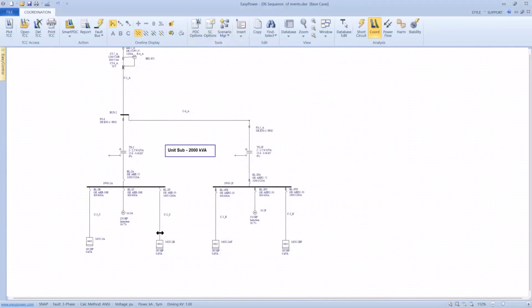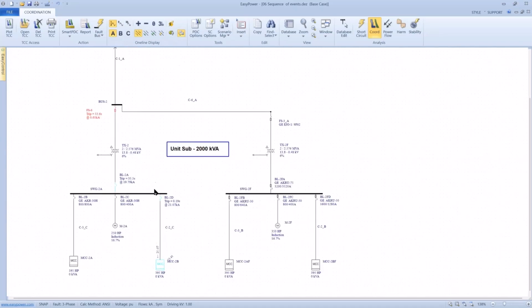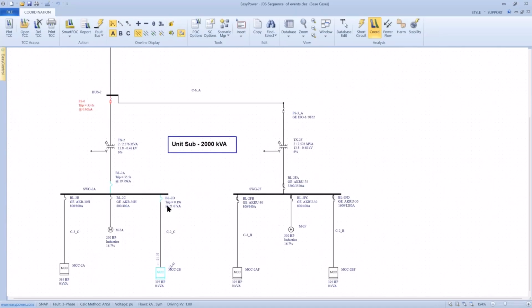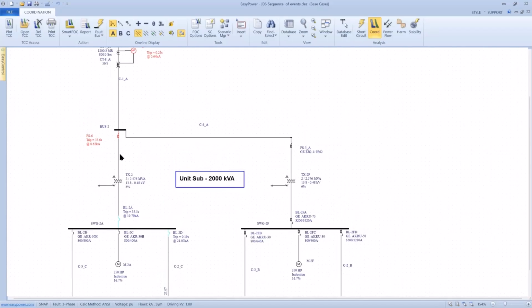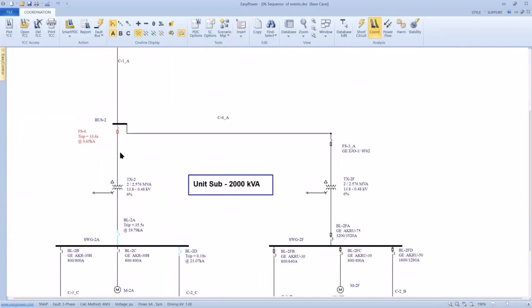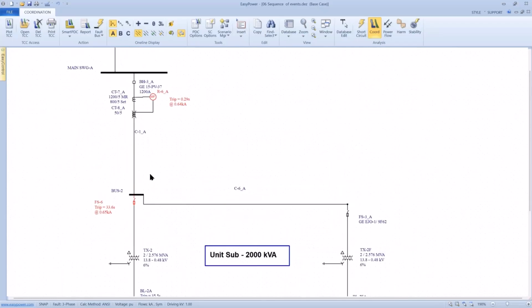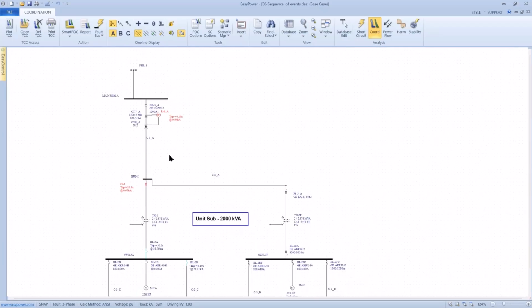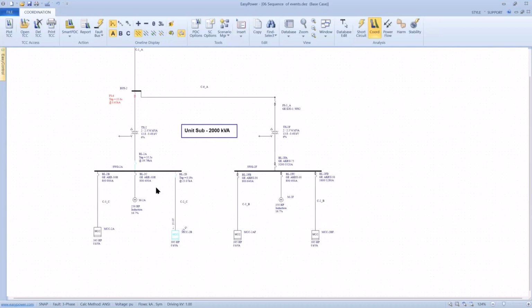Pick out a single bus, fault it, and then invoke sequence of events on the second row. I will see in chronological order: this breaker will trip in 190 milliseconds. This breaker will trip in 35 seconds. This fuse would have tripped in 33 seconds. And then the relay would have tripped in 290 milliseconds. So we have miscoordination just based upon this check.